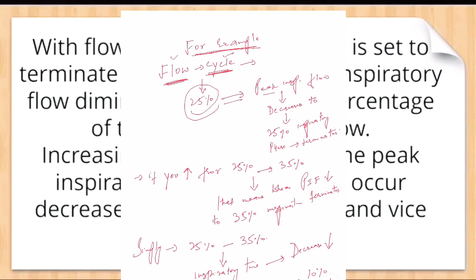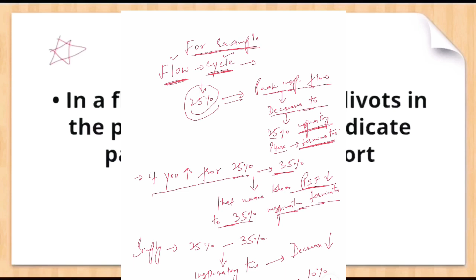Now, for example, if you have selected flow as the cycle variable, so if the breath is flow cycled, usually we select 25%. Now what does 25% mean? That means when peak inspiratory flow decreases to 25%, then the inspiratory phase will terminate. Now, if you increase from 25% to 35%, that means when the peak inspiratory flow decreases to 35%, the inspiratory phase will terminate. So simply, if you have increased from 25 to 35%, what will happen to the inspiratory time? It will decrease.